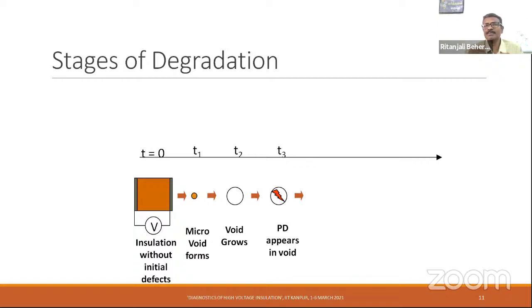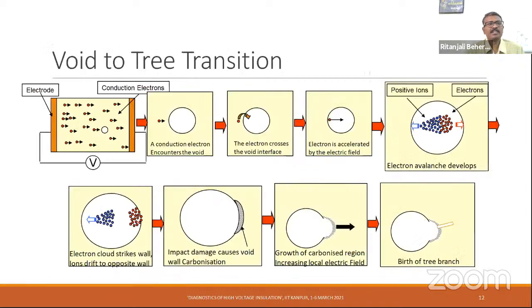The only thing is that it might not be at the detectable level. This could be less than 2 PC or whatever, but only beyond 2 PC are we able to detect it and then measure it by using a PD detector. So it will be taking place, but after the bigger void forms, the PD starts.